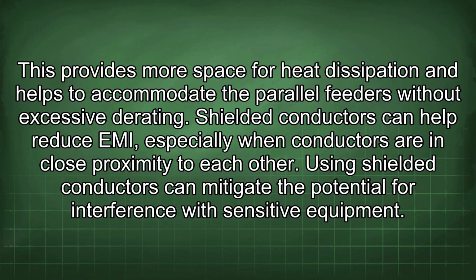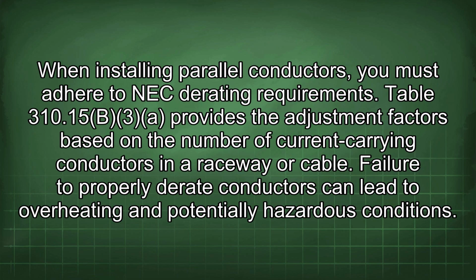Shielded conductors can help reduce EMI, especially when conductors are in close proximity to each other. Using shielded conductors can mitigate the potential for interference with sensitive equipment. When installing parallel conductors, you must adhere to NEC derating requirements. Table 310.15(B)(3) provides the adjustment factors based on the number of current-carrying conductors in a raceway or cable. Failure to properly derate conductors can lead to overheating and potentially hazardous conditions.